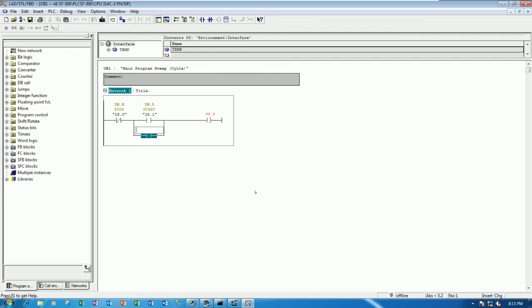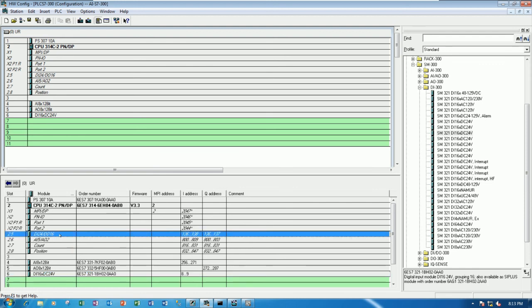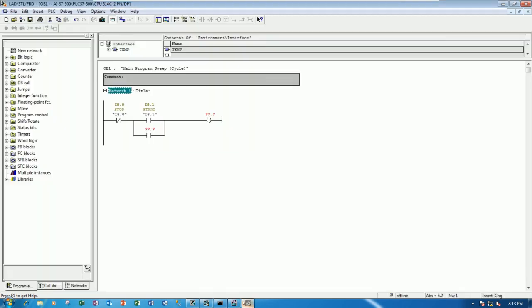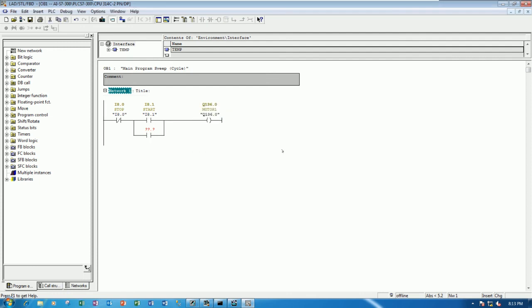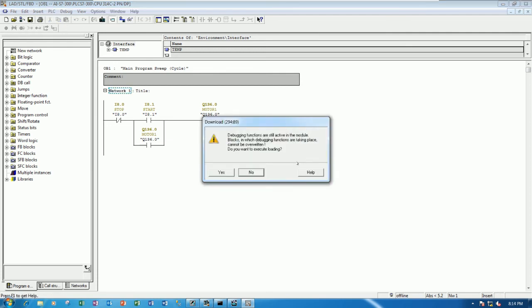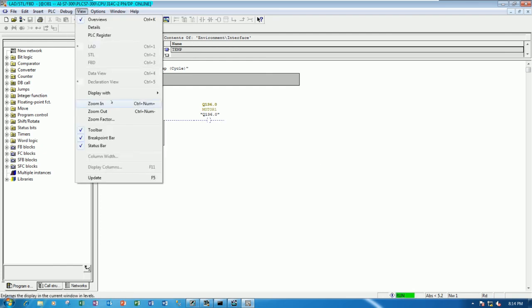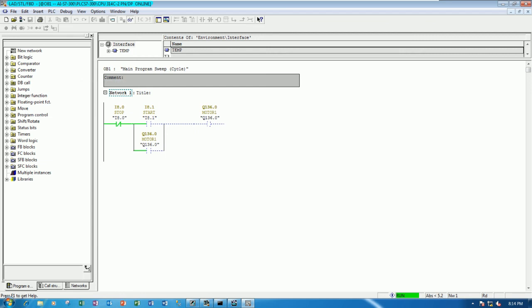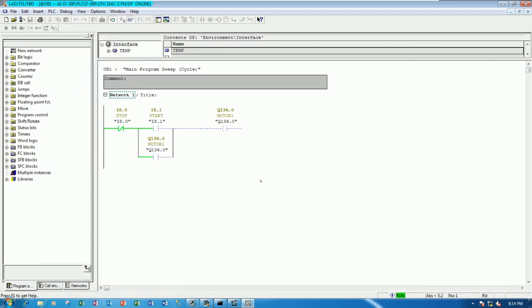And this one will turn on one output. Yes. Let's check the internal CPU output. Yes. It will start from Q136.0. Right. So example Q136.0 is turned on. When we push button start. Okay. Then it will hold the signal. And we can save the project and download program to the PLC. And then we can online for test. Okay. I will zoom in. Yes. Okay.